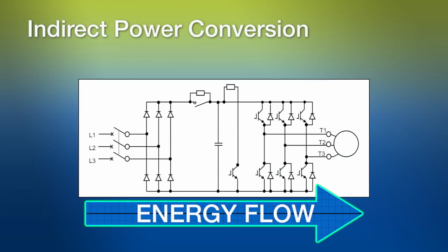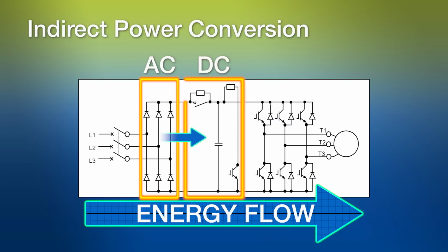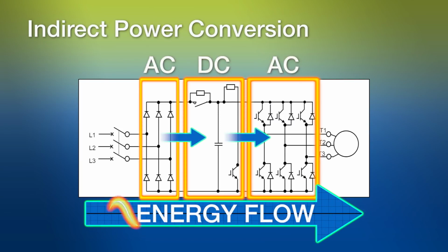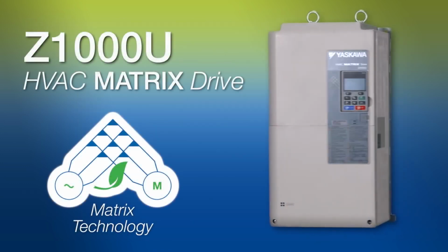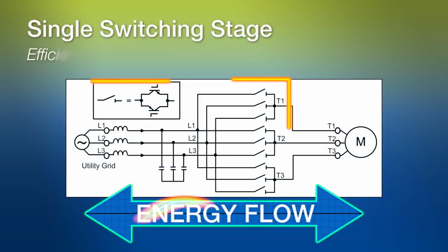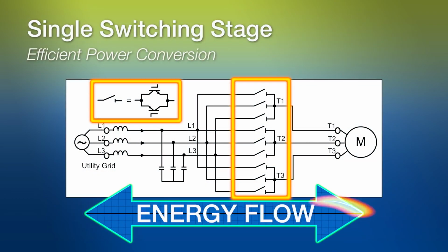Matrix technology is highly efficient because of the direct conversion of three-phase AC input power to the AC power required for precise control of the voltage and frequency output to the motor. Alternate methods involve 2 switching stages, one to convert AC to DC and a second to convert DC back to AC. This is called indirect power conversion. Each switching stage introduces losses into the system. The Yaskawa matrix drive uses a single switching stage to efficiently convert power.